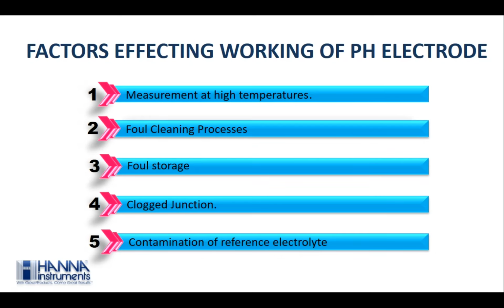Just cleaning by water is not enough. From time to time, one has to clean the electrode with a cleaning solution to clear the depositions formed due to some samples or the contaminants in the samples, which are not visible to the normal eye.